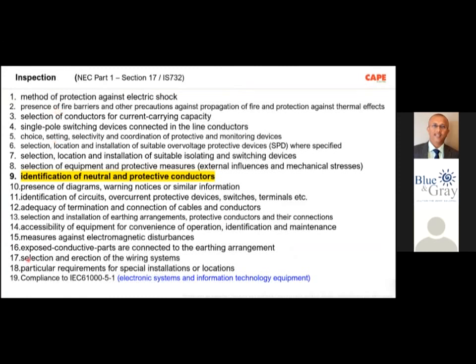Now, IS 732, for ensuring safety in an electrical installation, we are supposed to do several kinds of inspection. Number one, there are about 19 inspection points, out of which the 19th point I have added extra. It is probably not required in a normal electrical installation, but it is mandatory for a place where you have highly sensitive electronics, such as a hospital, a data center, a BMS system, instrumentation systems and so on. So basically, inspection consists of 19 points. Out of these, point number 2, for example, is presence of fire barriers, other precautions against propagation of fire, and protection against thermal effects. All these things are directly connected to fire protection.